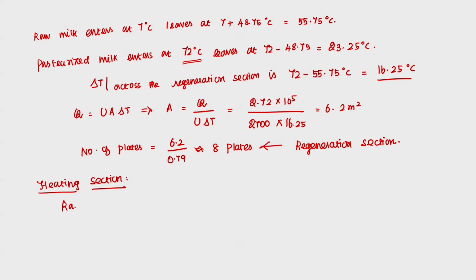The raw milk which comes out of the regeneration section at 55.75 degree centigrade is getting heated in the heating section and leaves at 72 degree centigrade. Here if I want to calculate the area, the formula I would use is Q upon U del T, where del T is the logarithmic mean temperature, ln of del T.